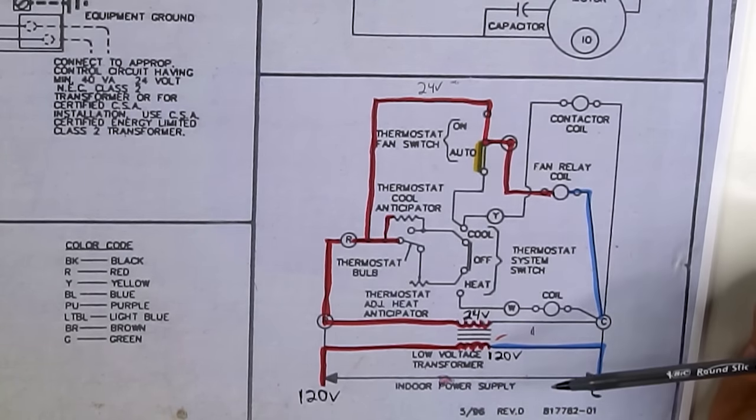One note I forgot to point out: it says 'alternative double pole contactor.' Some units may have a double pole contactor — L1 to T1 will have a break and L2 to T2 will also have a break, so there will be normally open contacts on both sides. And last but not least, even though this is field wiring, we have our ground wire — the green ground wire from the disconnect whip goes into the screw right there.